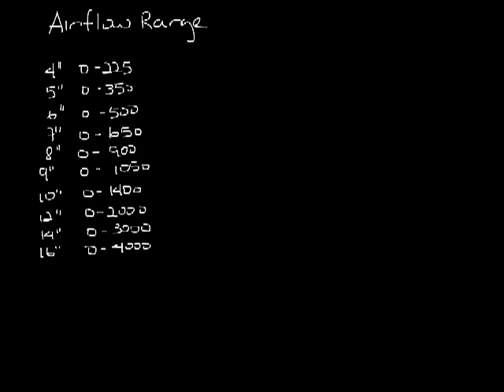So let's talk about the low end first. Zero is obviously a closed damper, but can you really put 1 CFM through a 10-inch inlet? Well, yeah, probably you can, but you won't be able to measure it. So manufacturers publish minimum CFMs.